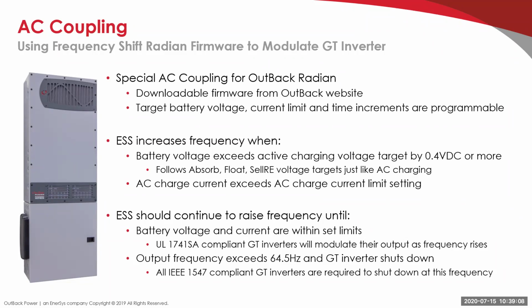After all these years of utilities saying, no, you can't connect to our precious grid, you have to synchronize for 5 minutes and then maybe we'll let you connect, now they're saying, well, gee, the solar density is such that all these solar systems out there could actually help support the grid. So one of the support functions they have is something called frequency watt. If there's too much energy on the grid, the utility can actually increase the frequency and get all these grid-dependent inverters, which are about 90% of the solar generation out there that don't have storage, to reduce output. That's also an opportunity for you guys, I guess, to add storage. And then they'll increase that frequency.